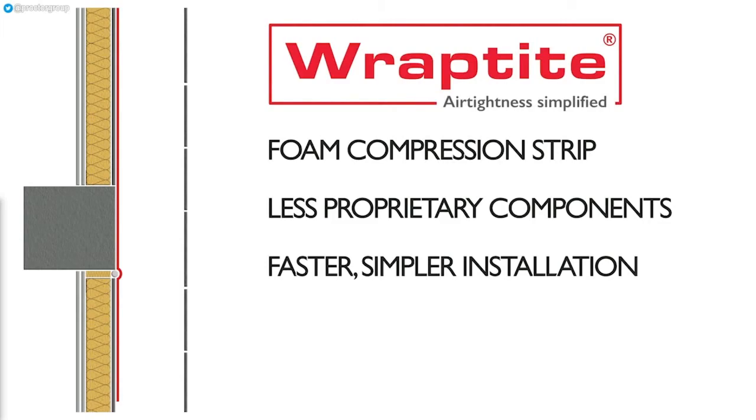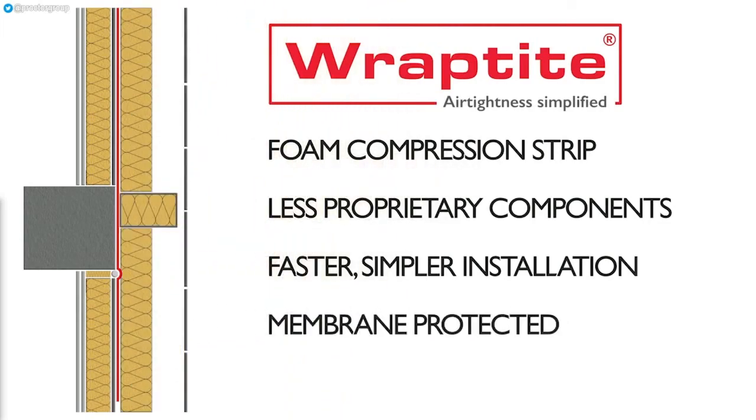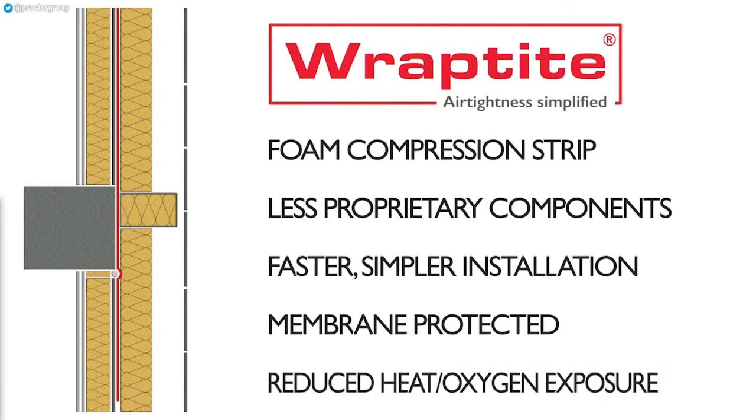With the airtightness aspect dealt with, the outer layers of the construction can then be applied, with a permeable and incombustible insulation layer preventing fire spread both itself and by limiting the potential for the membrane to be exposed to flame. This, combined with the fully adhering backing of the Wraptite, reduces the potential for both heat and oxygen to reach the membrane from either side, removing the two key aspects of the fire triangle required for combustion. Fire breaks and cavity barriers can then be added without too much concern as to how they affect air leakage.